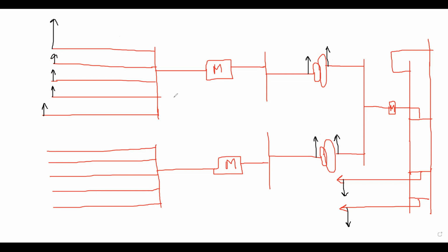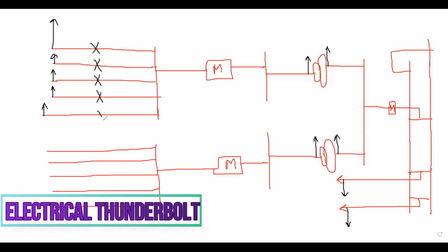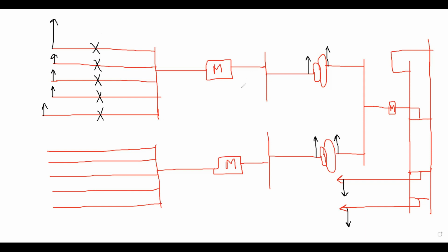Okay. Now, next what I told: for every feeder, at every bay, at every stage, we have to consider it as a bay. So to protect this bay, we require a breaker. If you want to give the breaker here also, you can give. Mostly for 33 kV, for the metering, a breaker is not required because you can't see any failure in this mostly. It is only a meter, right? So not required. And for the sectionalizer, we require the breaker.